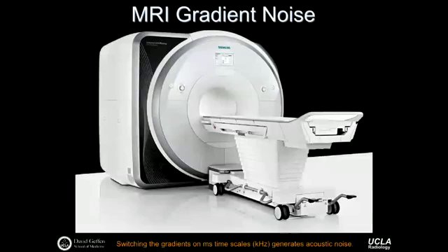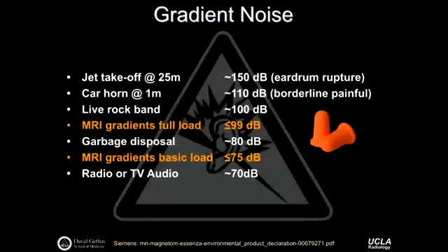MR, just like any imaging modality, you always have to make consideration for the different safety aspects. The gradients induce a couple different safety concerns. One of them is this. If you've ever been in an MR scanner, it's loud, right? It's quite loud. If we look at sort of the decibels of noise generated by the MR system, it's somewhere on the order of listening to a live rock band. I don't know who they went and listen to, but you get the idea.